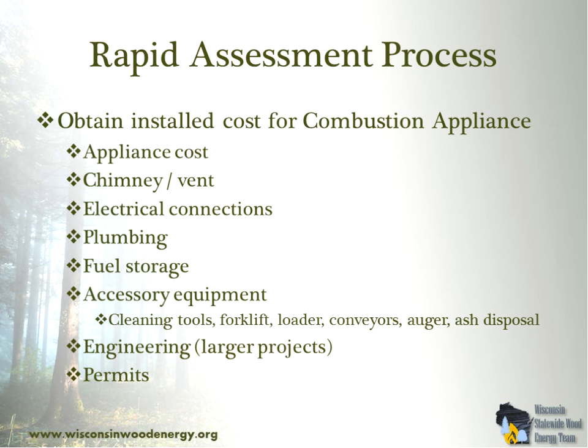So I got $4,875 in cost for my LP gas. My wood is going to be 12.8 times $200 per ton. It's going to be $2,560. So I subtract the two, and I'm going to get a savings per year of $2,315. So that's the money I have to pay for any investment that I'm going to do. So that has to cover the equipment cost of converting to a different fuel.